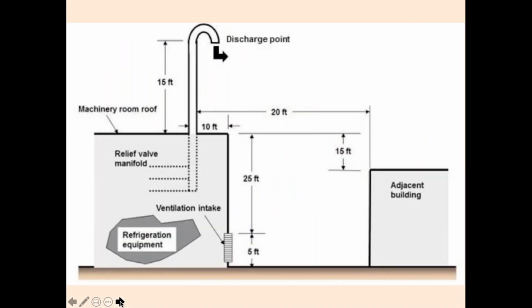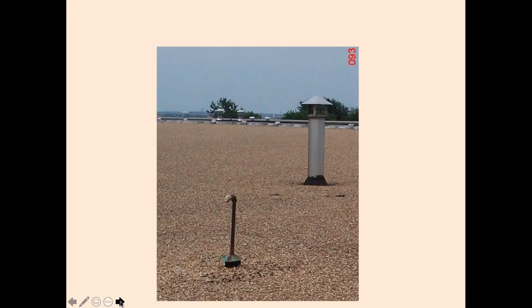Always, as I mentioned last time, the safety valve outlet discharge point should be outside the machine room, 15 feet above the maximum occupied height of the building. So even if the safety valve blows, the ammonia will go to the atmosphere and will not cause any harm to persons who occupy the buildings. This is the way the safety valve outlets are shown, with a cover on the top so that no dirt or dust falls inside, or with a U bend, for the same purpose.